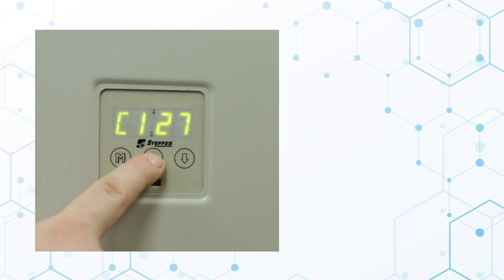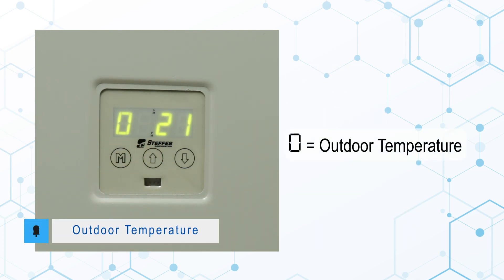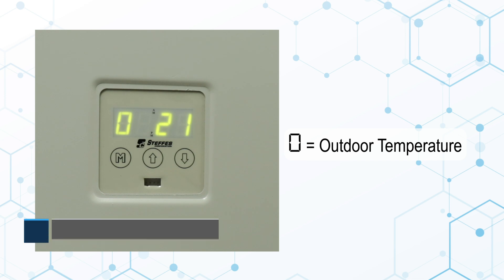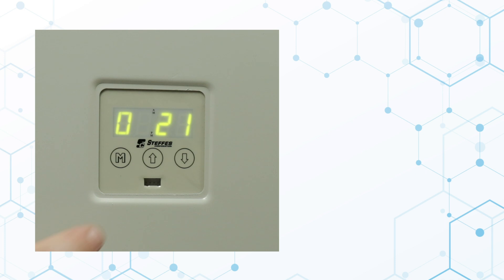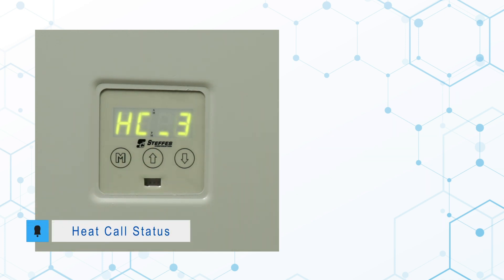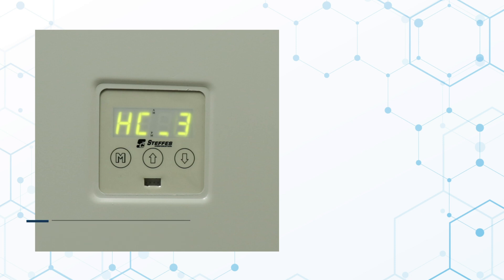Press and release the up arrow. The display will show O and a number, indicating the current outdoor temperature as read by the hardwired outdoor sensor or PLC transmitting device. Press the up arrow again. The display will show HC and a number, indicating what stage of heat call the furnace is currently receiving from one or more thermostats in the application.